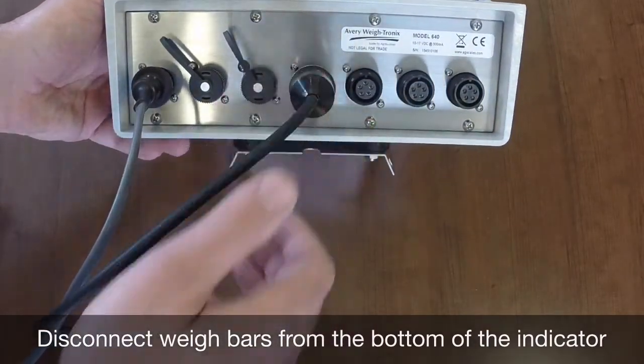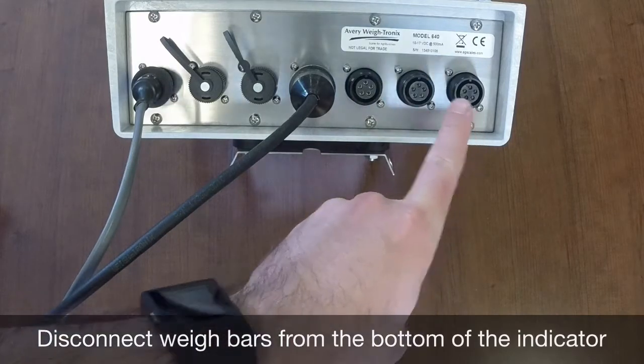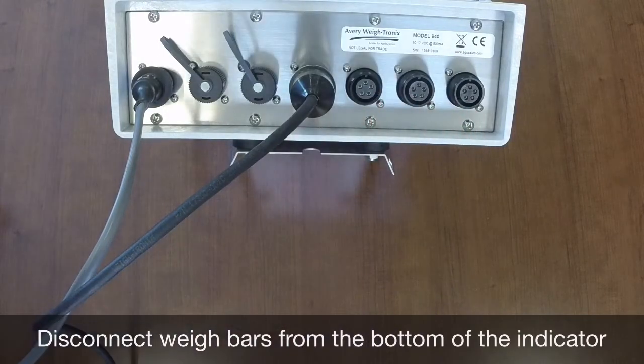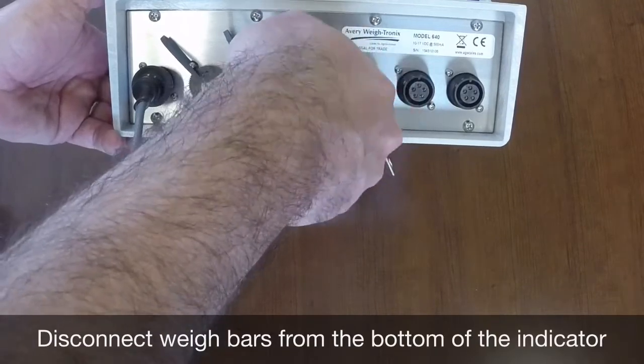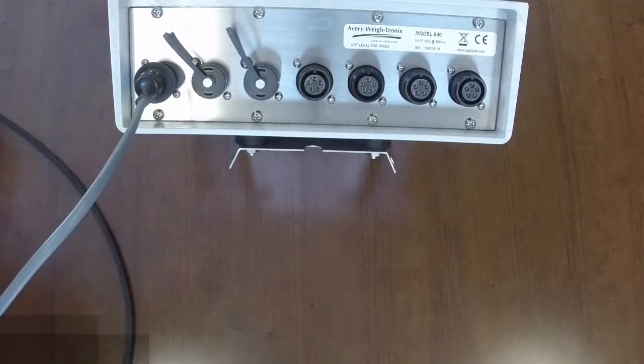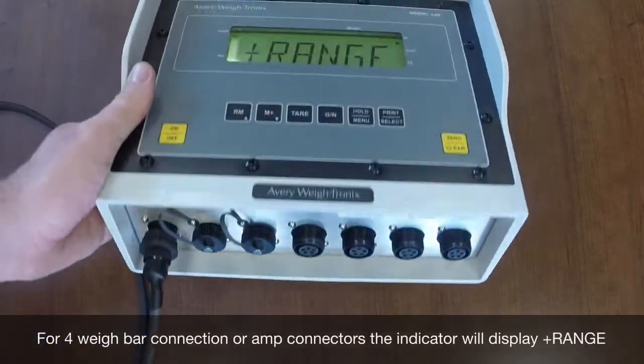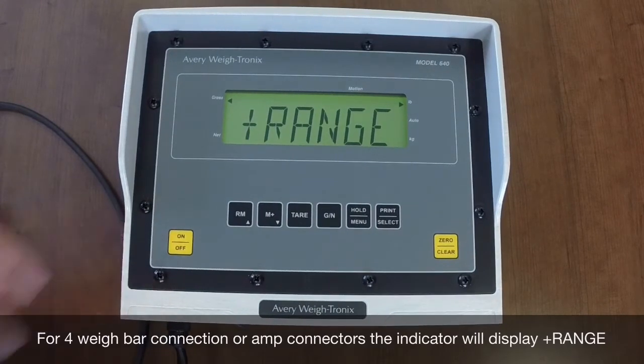So now that we have that out of the way, let's get into some troubleshooting. First, disconnect the weigh bar connections on the indicator. If all the weigh bar connections go into the indicator, disconnect all of them. If there is only one connection, disconnect it. When you disconnect the weigh bar input to the indicator and you have a 4-weigh bar 5-pin base, single 5-pin connector, or amp connector, it will be normal to see plus range on the screen. If you have a 3-weigh bar 5-pin base, you should be able to zero out the indicator.